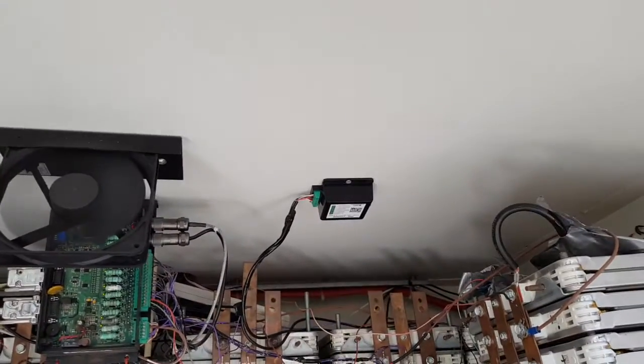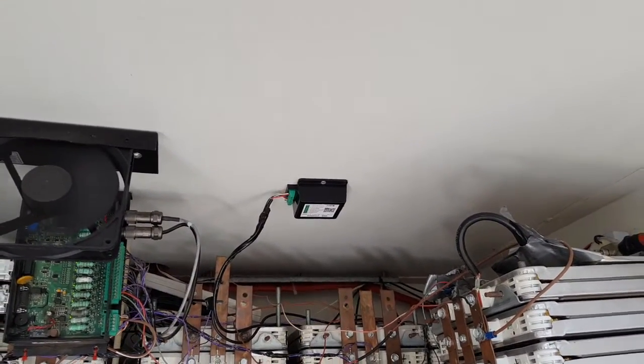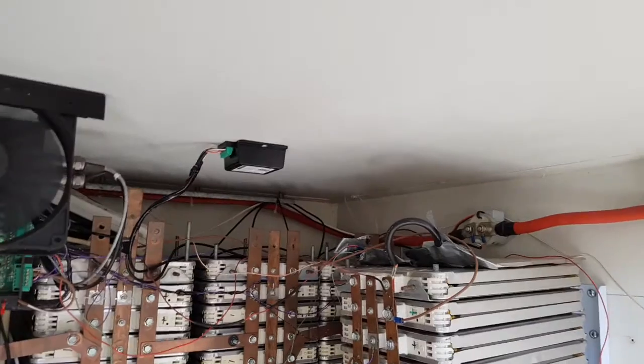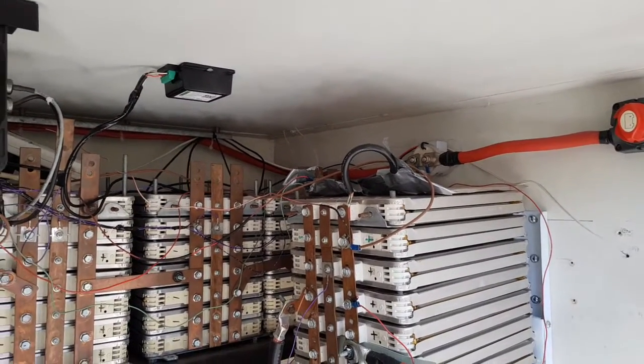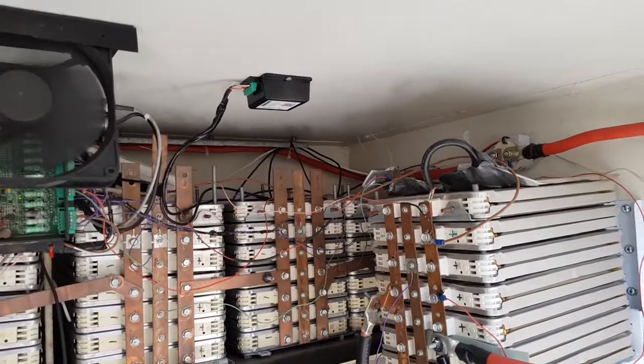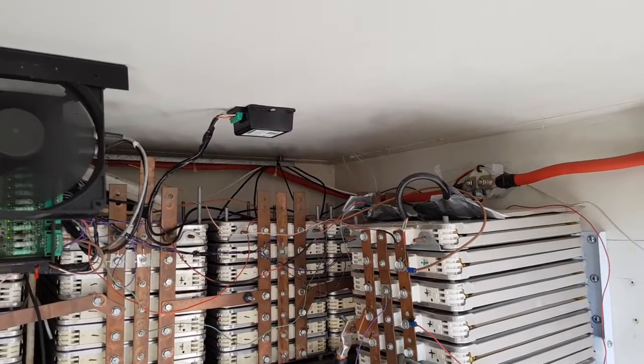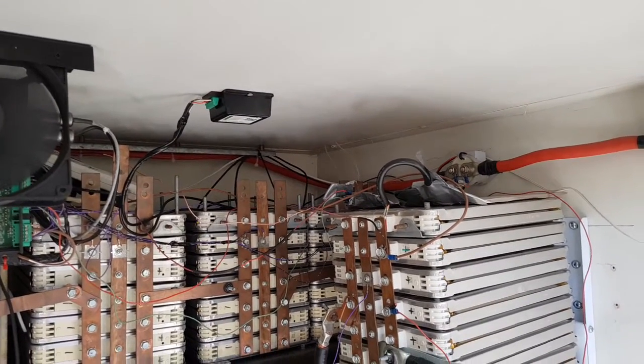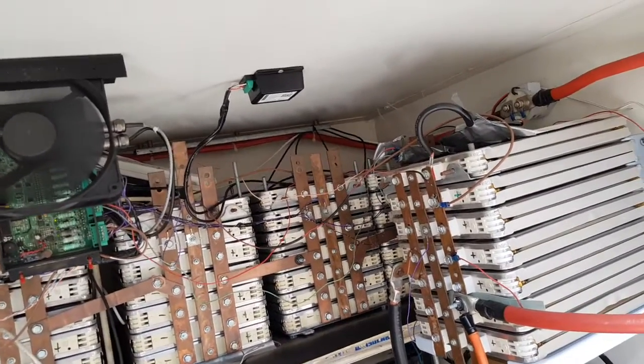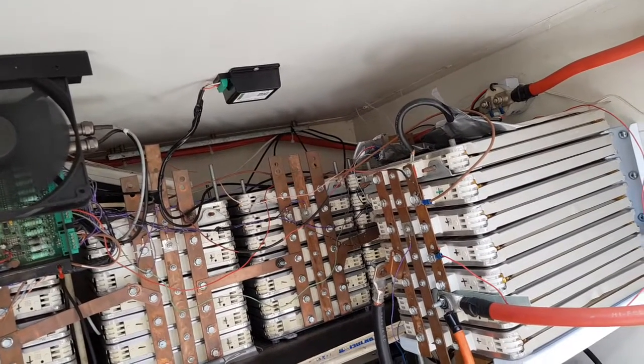What else you got? Pre-charge, which is that little relay up there, and what that does is pre-charge the capacitors inside the Sunny Island units before they turn on. Sunny Island inverters are quite chunky, so if you just turn it on straight away, the draw would be enormous - that's what that basically does.